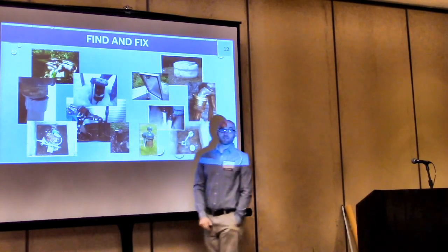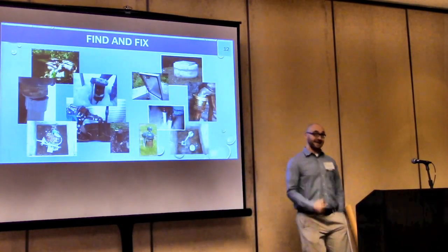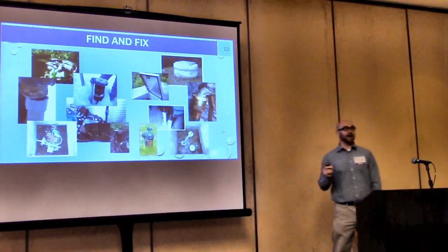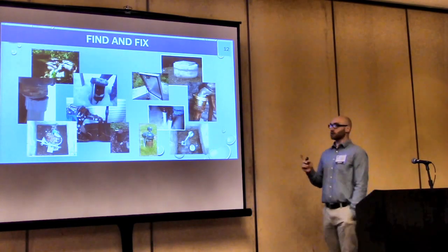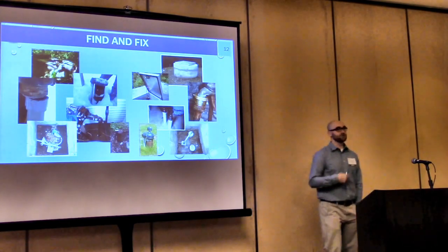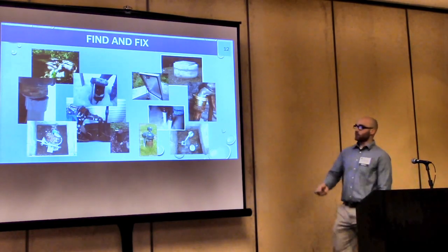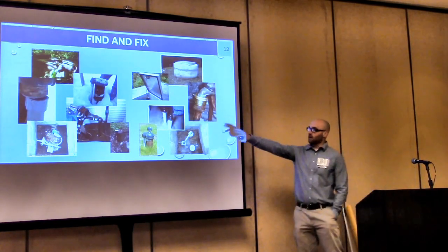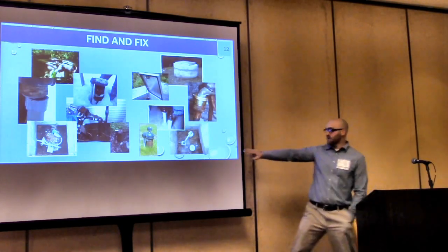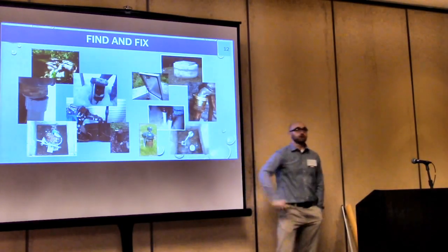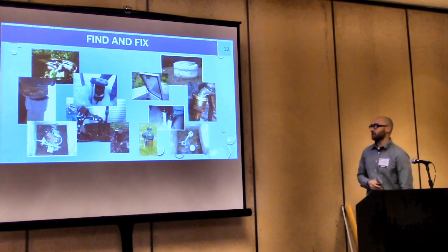And then the problem is that the frost isn't nice and doesn't take it back when it leaves. It's going to stay like that. And if it stays like that all summer, little creepy crawlies are going to get into your well. And if you're a small system without treatment, then that's into your system. So ultimately, we want to see a transition from broken, cracked conduits to a nice sanitary, modern sanitary well cap.